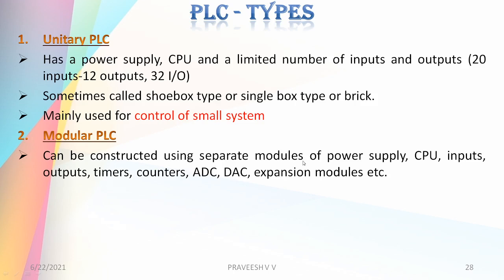When it comes to modular PLC, it can be constructed using separate modules of power supply, CPU, inputs, outputs, timers, counters, ADC, DAC, expansion modules, etc. You can include whichever modules you want — if you need timers, include the timer module; if you need a counter for your particular application, include the counter module. There is flexibility to choose between the modules you are going to use for your particular application.